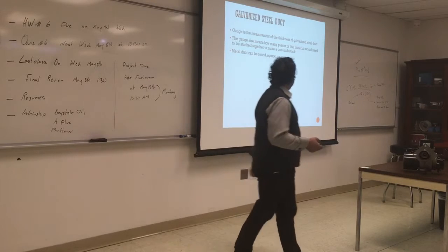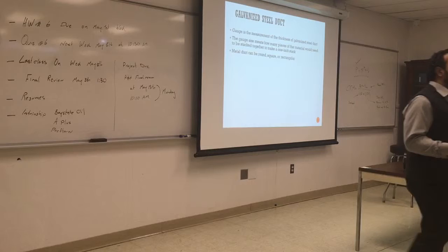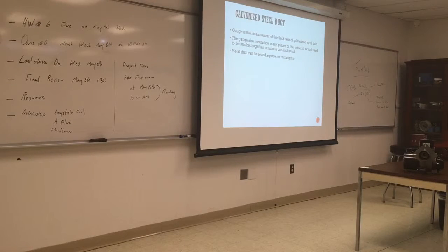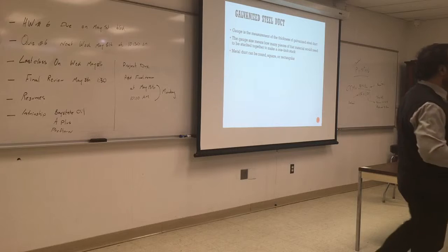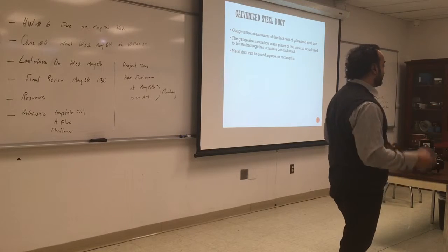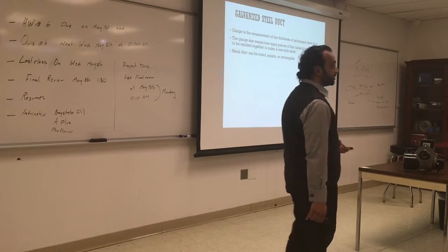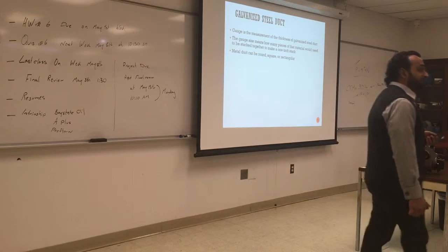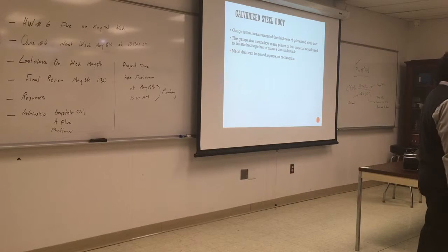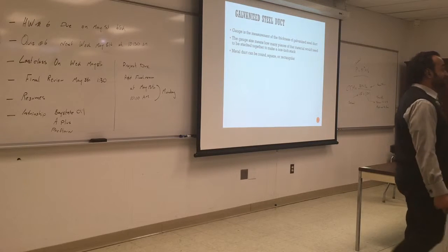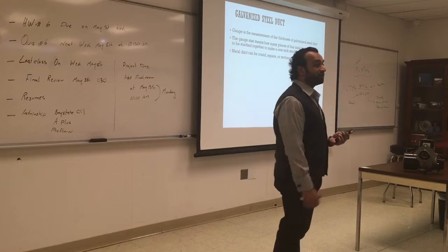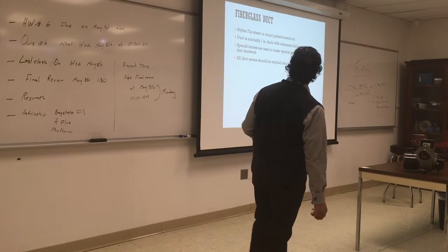Metal duct can be round, square, or rectangular, and a person with a sheet metal certificate knows what the gauges are and how much space you can span without having support, because the gauge can support itself. And they have a lot of general rules for cutting and angles and pitch. So that's what the sheet metal is about. That's what the certificate will give you. The art of making sheet metal look nice and having good craftsmanship, that's up to you. And that's why some people charge more than others.